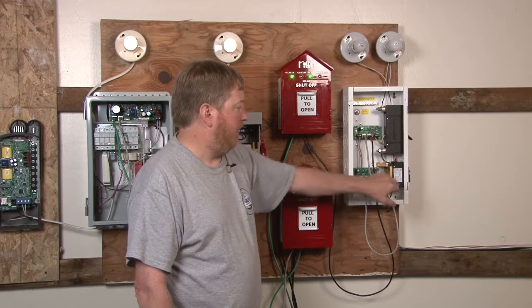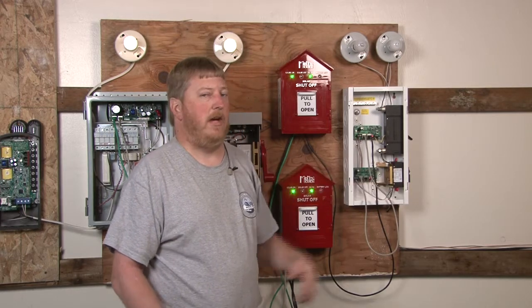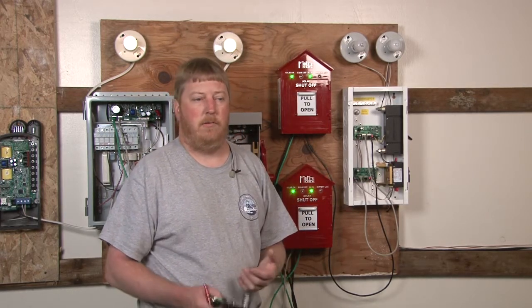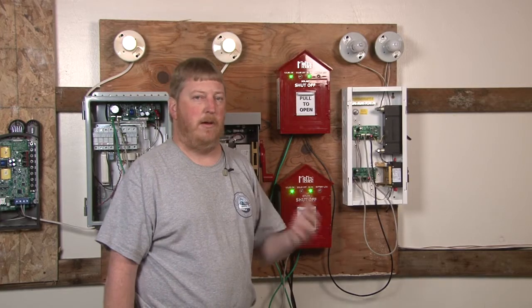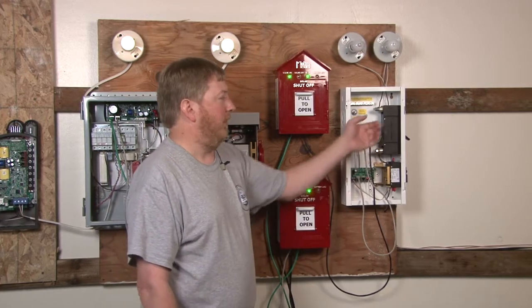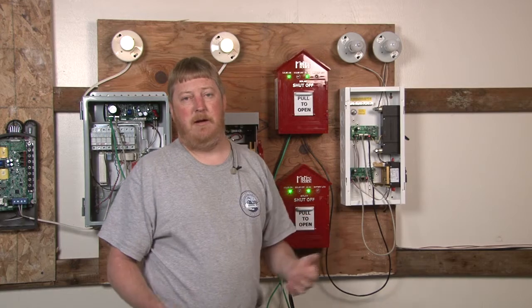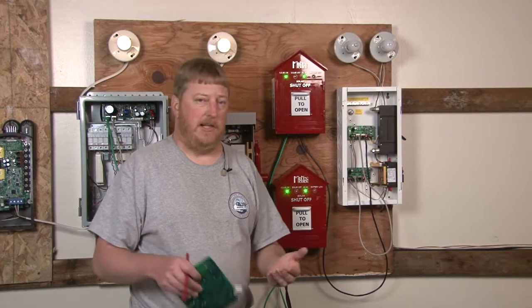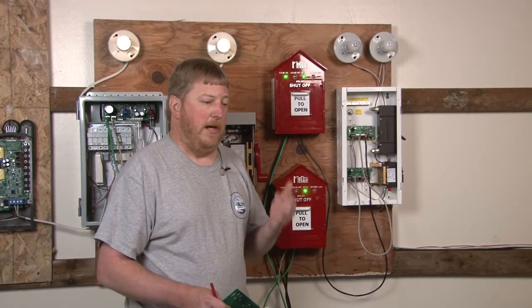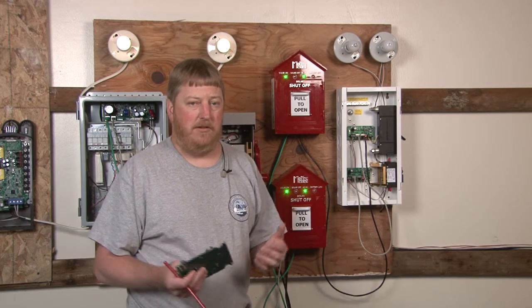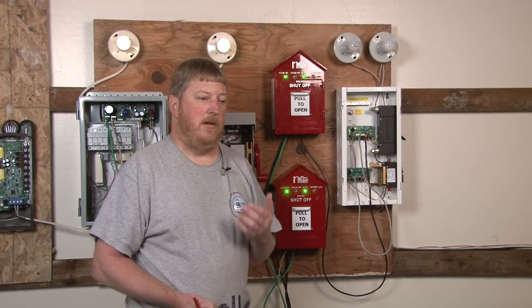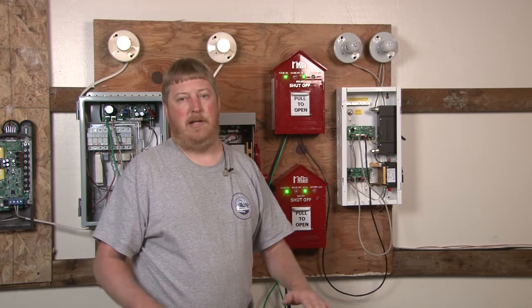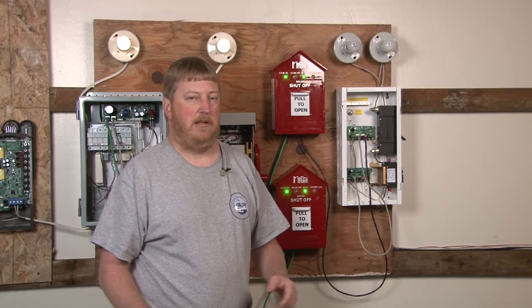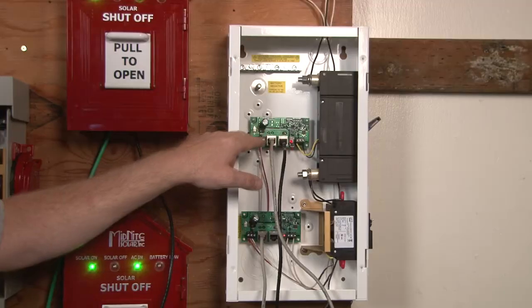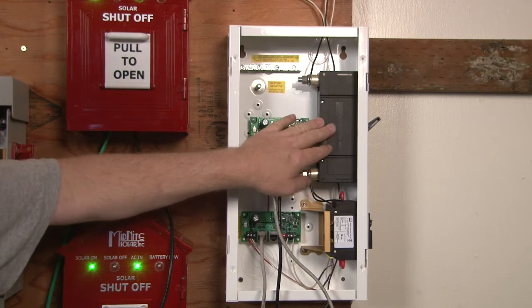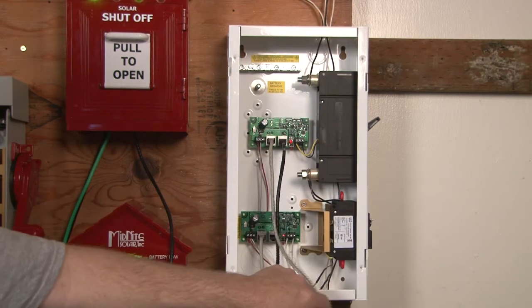Each one of these modules controls a shunt trip breaker. We have shunt trip breakers in every flavor. We have DIN rail, we have panel mount, we have them all the way up to 250 amps. So we can turn off virtually anything that's battery powered: inverters, loads, charge controllers, whatever the case may be. The reason for that is the rapid system shutdown requirement in the code is going to require that the whole system be brought down to a safe voltage within so many seconds with a single push of the button. So this accomplishes that by tripping off each switch independently.